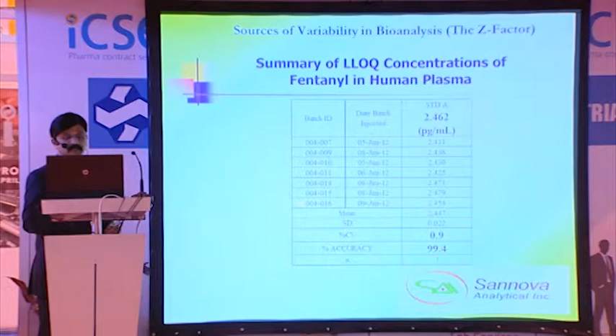This is an intra-assay precision and accuracy batch. As per health authority regulations, at the LLOQC level it can be up to plus or minus 20, and at low QC, mid QC, HQC level, the accuracy can be 85 to 115. So we got about hundreds, and percent CV is 1 to 2.9. This is PA1. And in another PA batch, the results are about 99s and 1 to 3. And in another PA batch, the results are 95 to 100 and 1 to 5.5. These are 3 different PA batches. And if you look at the inter-assay precision among those 3 PA batches, they are about 98 to 100 and 1 to 4. So this gives an idea about the quality of the method.